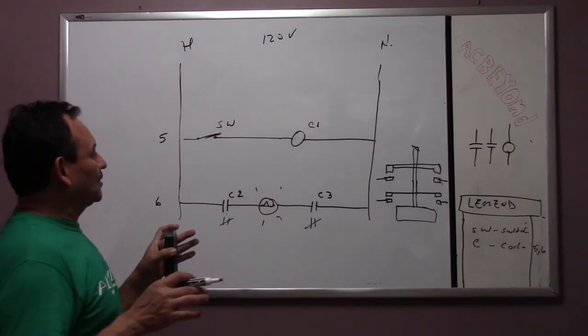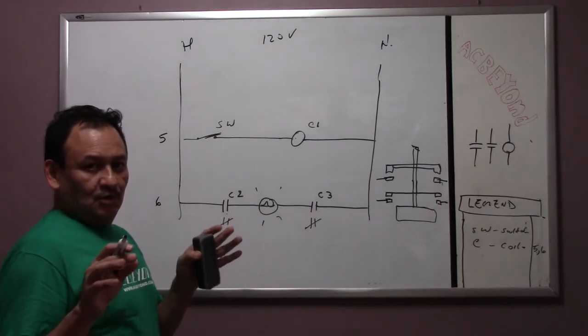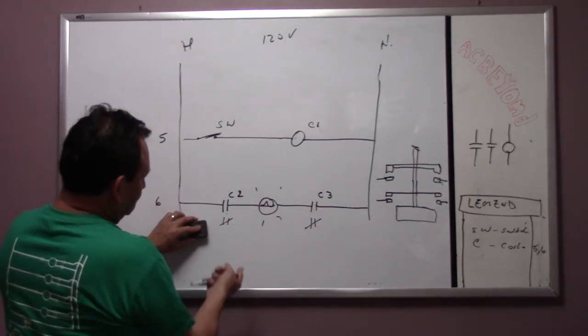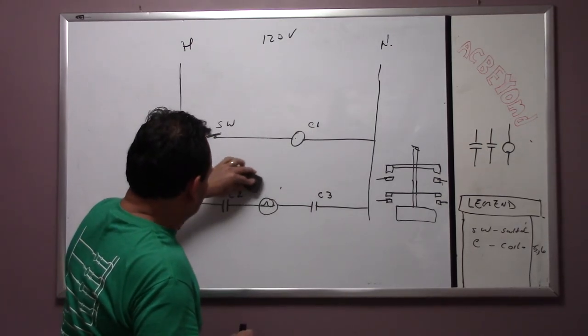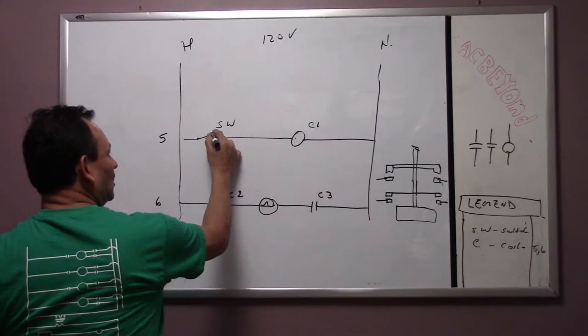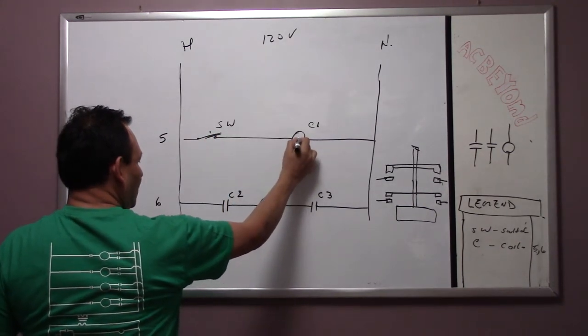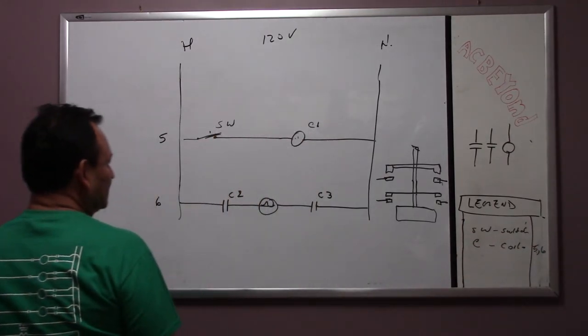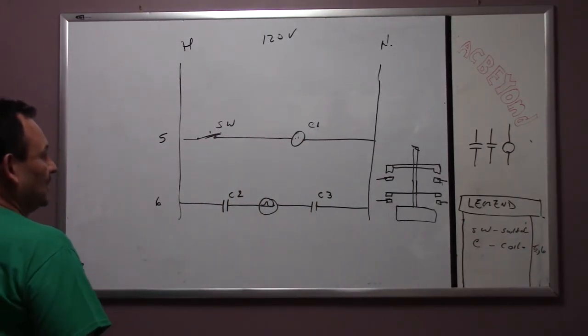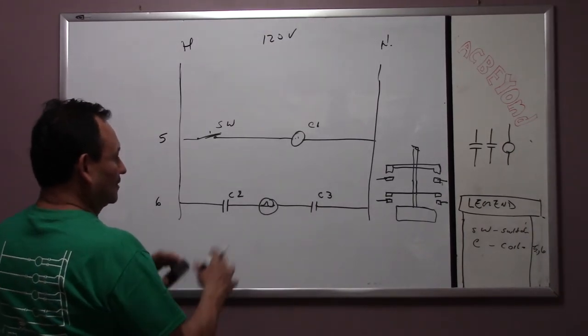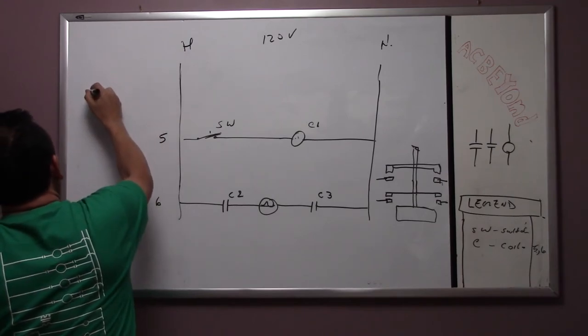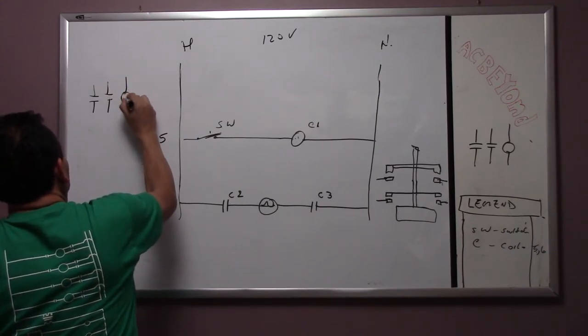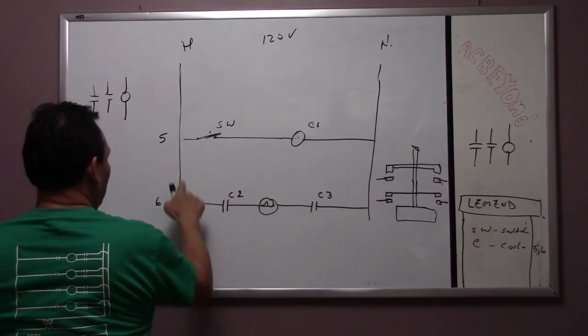The way to read a wiring diagram is you have to look at it with no voltage and imagine what happens when the switch closes — because they can't show you it closed since it's normally open. You have to visualize: switch number one closes, energizes the coil, the coil closes the contacts. On the legend the coil will show five and six.